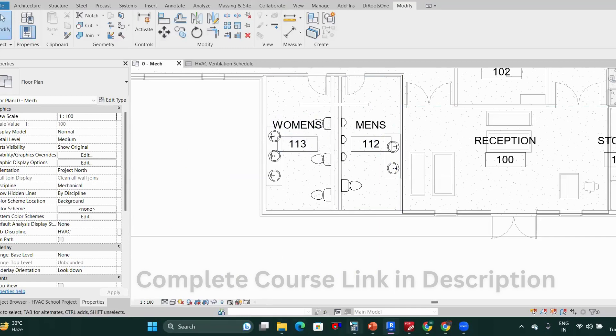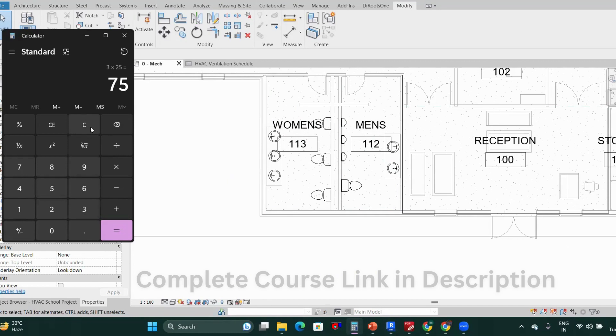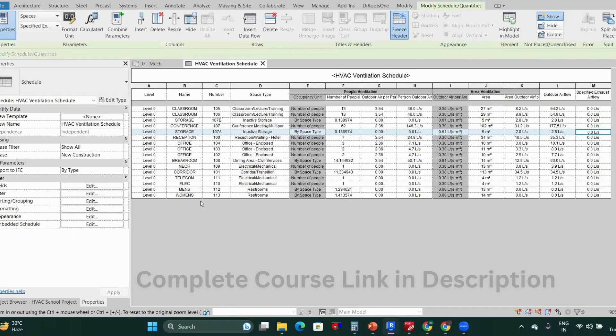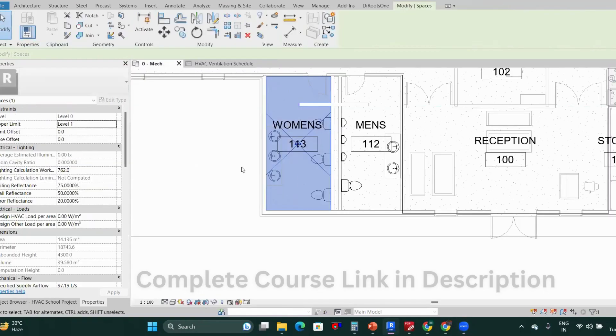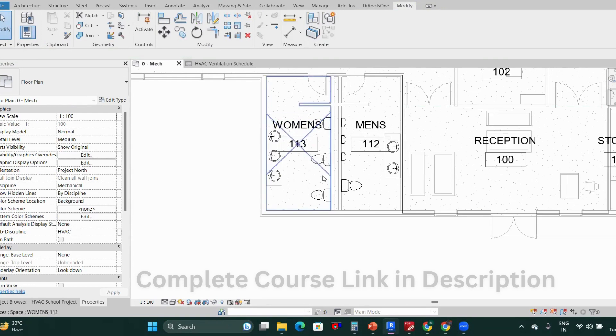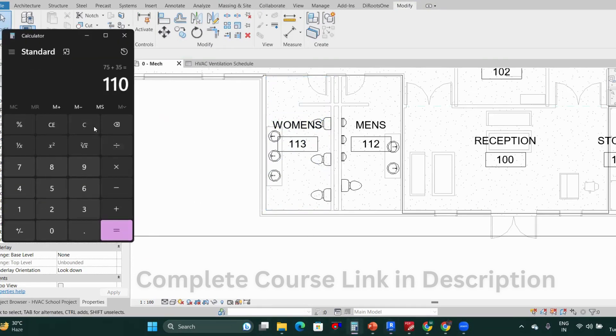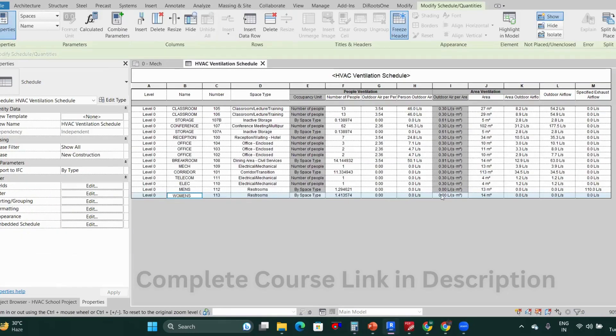For the men's toilet: three urinals at 25 L/s each equals 75, plus one WC at 35 L/s, gives a total of 110 L/s. So for the men's restroom, we'll take 110 as the exhaust. For the women's toilet, we go to the floor plan — there are only three WCs. Three WCs at 35 L/s each gives 105 L/s. So 105 is the exhaust rate for the women's toilet.